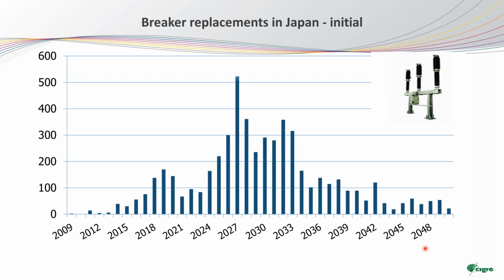As an example of the importance of asset management, I took this slide from one of the CIGRE technical brochures, and it describes an experience from the Japan National Grid. They decided to put a long-term plan for the old circuit breakers in their network, from 2009 till 2048. When they put this plan to replace the circuit breakers, they found out that the number of breakers to replace per year is not constant, and it changed significantly. And this, of course, will result in a variable allocated budget per year, which can be a nightmare for any asset manager to deal with.